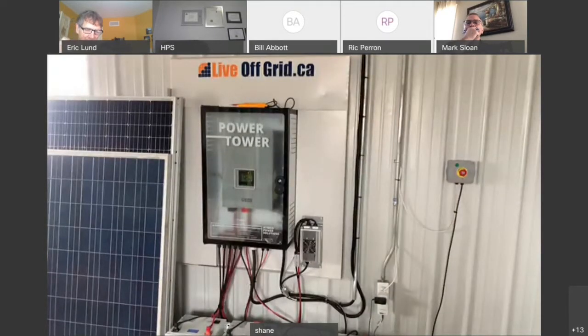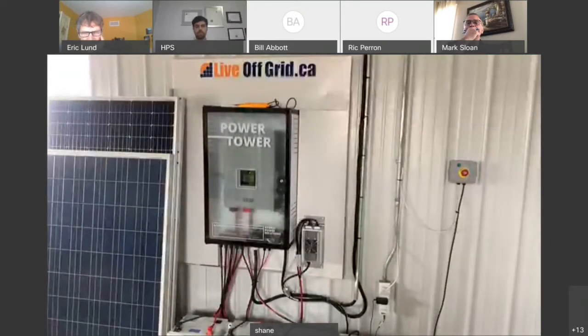I think with everything we went through, it turned out really nice from an installer's point of view. The specs on it, if you guys don't know: it's a 6 kilowatt inverter. There's a 120 and a 120/240 split phase version. On the 120 version, you have a 40 amp output breaker on it, so you could actually have 6 kilowatts at 120 volts. On the 120/240, you have 6 kilowatt between the split phase, so you're coming out at about a 30 amp breaker.